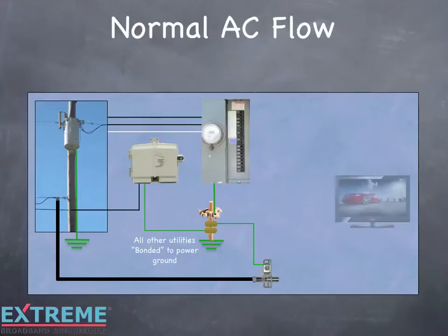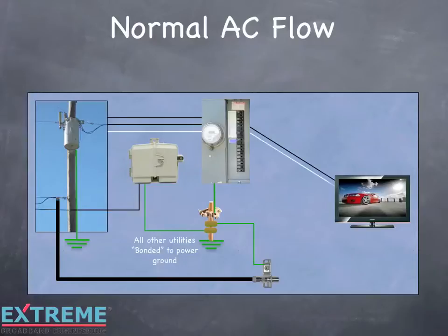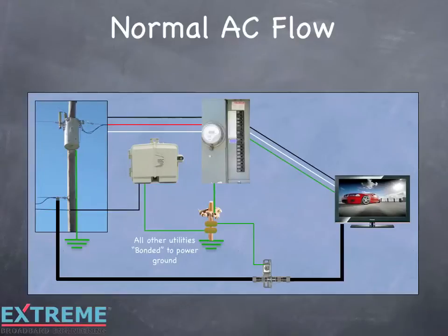In this example, we are showing one circuit that is run to the TV. From the circuit breaker there are three electrical wires run: a black which is hot, a white which is neutral, and a green which is ground. From the cable ground block, the cables run to the TV. Through the TV tuner, the power ground and cable shield again come in contact with each other. The normal AC flow goes from the hot leg of the transformer, through the power meter and circuit breaker panel, through the hot or black wire to the TV set. It then travels back through the neutral or white wire, through the circuit breaker panel and power meter, through the neutral, back to the transformer.